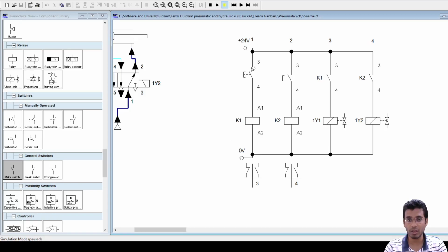You can see here, all your input elements, your switches S1, S2, and all those things are here, and all my 1y1, 1y2, as well as energizing my relay. A contact of a relay is an input element, whereas the relay itself is an output element. Fine. So all of them are at the bottom. Again, I told you my circuit will always flow from left to right. If you see, I started making the circuit from left and went to the right. And then I told you all the control elements will be towards the left, and all your main circuit elements will be towards the right.